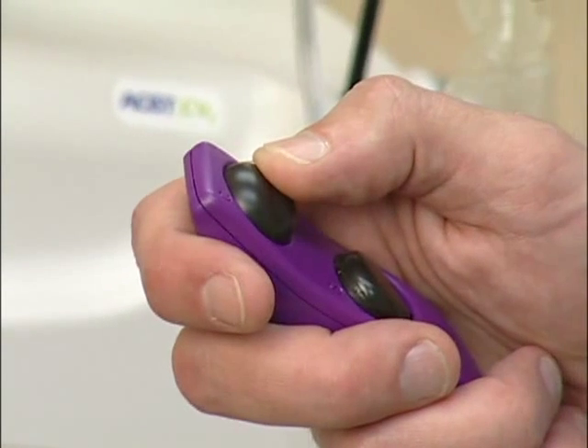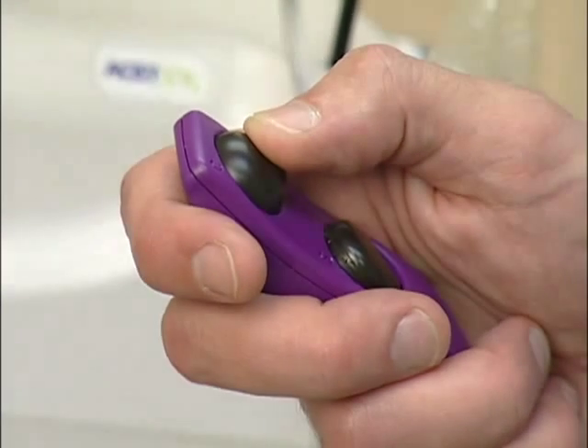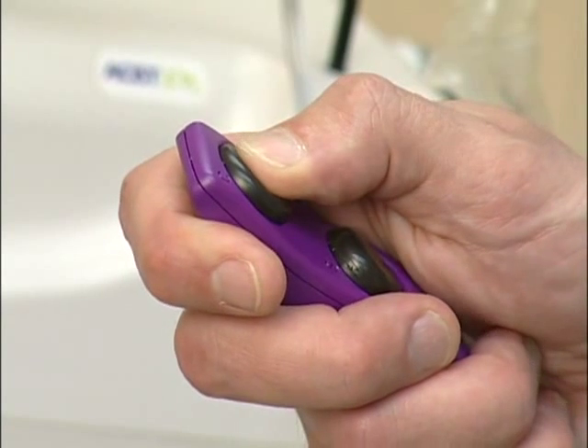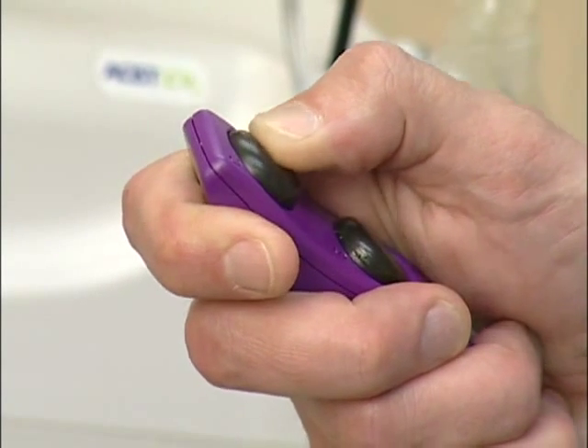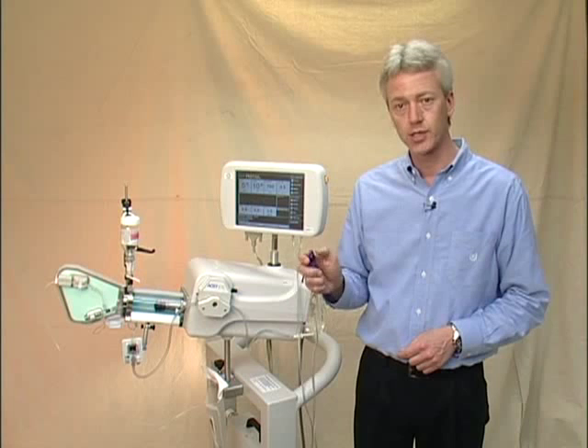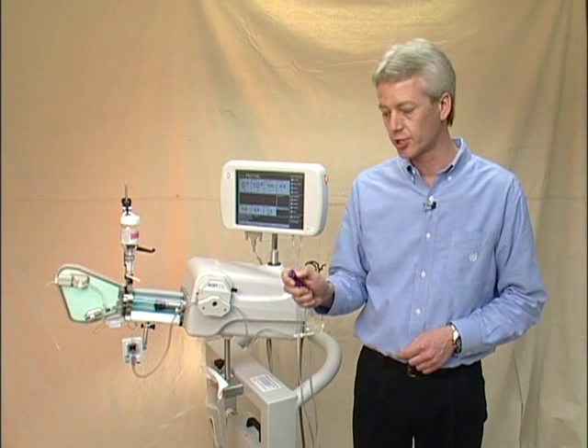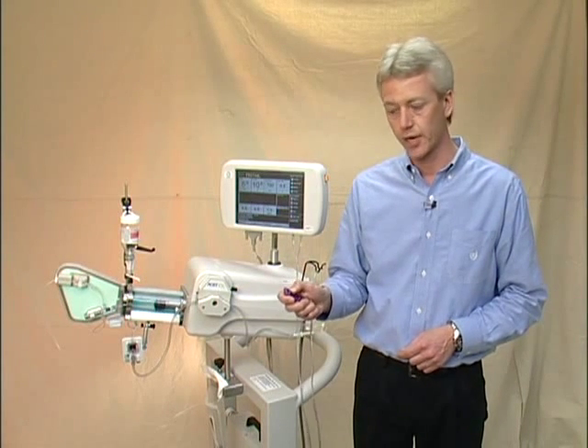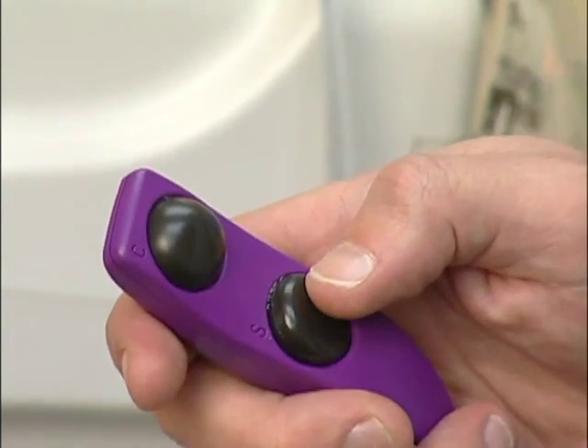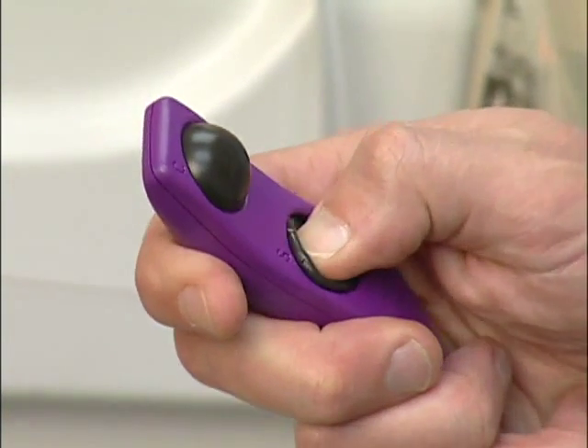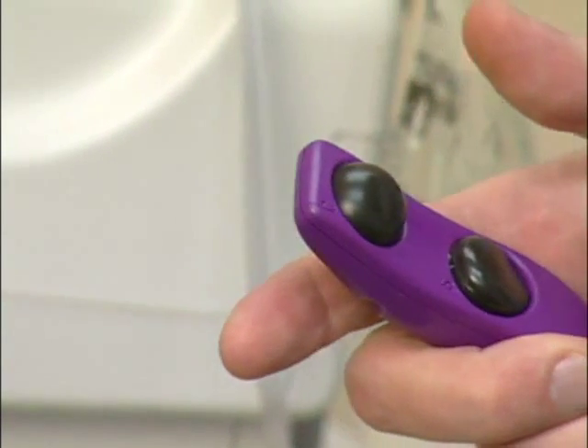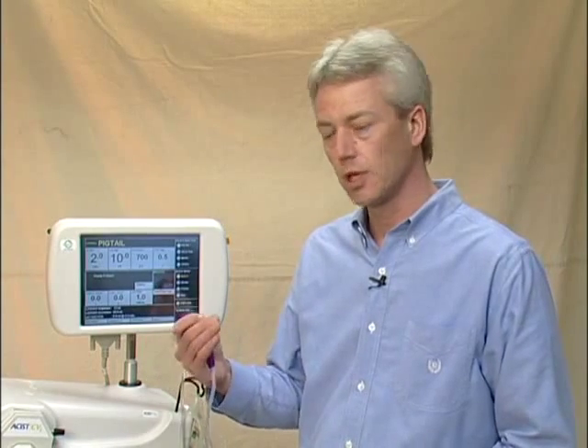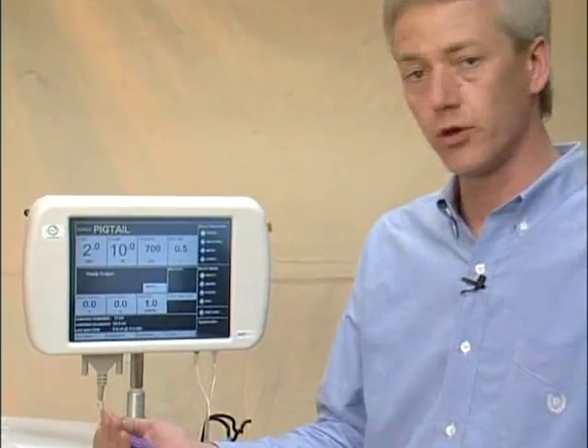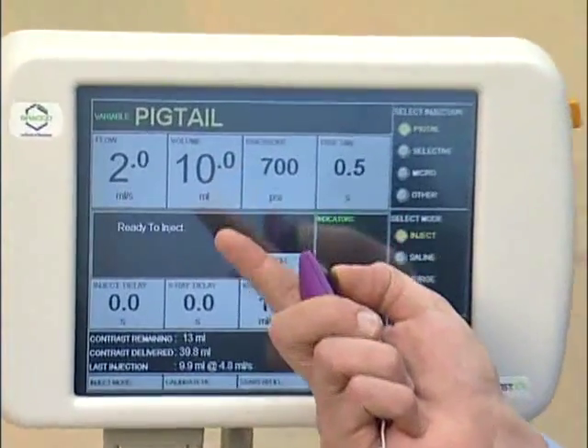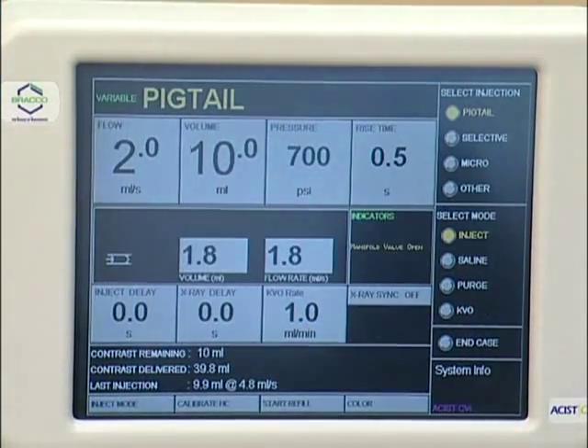One of the unique features of the hand controller is that it works much like the gas pedal in your car. The deeper that you press on the button, the faster the flow rate, up to the selected limit. This allows the operator to give very small injections at a variable control rate. The saline button is just an on-off switch. Once we'll start the saline flush and once we'll stop the flush. One nice feature of the system is the auto refill. So once this injection is complete and it brings me with a volume which is less than what is selected on the screen, you'll see the system automatically refill.